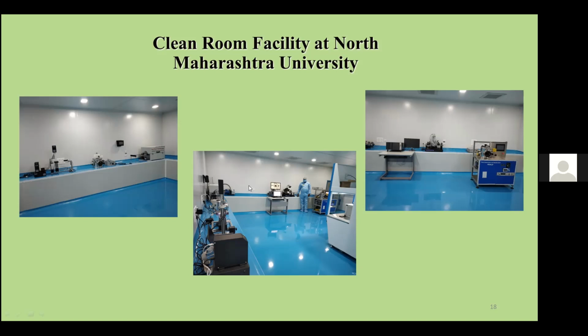And one more thing is, when we decide to make the clean room, we should count things like how many gas lines we need inside the clean room, how many outlets of gas like vacuum pumps and other things. Even power supply is also an important thing, because we fit a lot of instruments inside the clean room. So we can make a list of instruments and what kind of power supply is needed for each instrument. We should make the list as per our requirement.